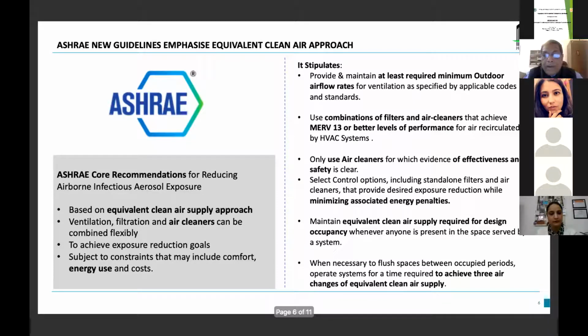And there are two more points which need to be highlighted. Earlier we used to have demand controlled ventilation to reduce the outdoor air requirement. But now, if you see in the guidelines, maintain equivalent clean air supply required for design occupancy. So we have to maintain the air supply as per the design occupancy at all times. And here the equivalent clean air supply will be very valuable to solve the problem.